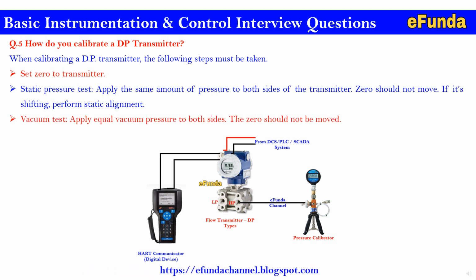Vacuum test. Apply equal vacuum pressure to both sides. The zero should not move. This is how the transmitter calibration is done, where one has to ensure that the zero value of the transmitter is set, and for that one should understand how the HART calibrator or communicator is used, so as to see the actual zero setting of the transmitter.